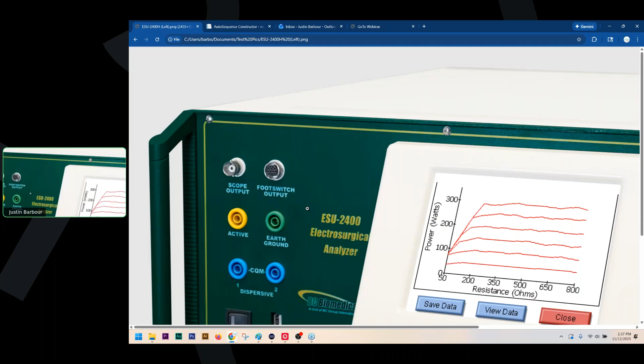And maybe from there it tells you, okay, plug it now into monopolar port 2. And it automatically will set your ohms for your load. Let's say for your REM, it will set your ohms load internally, and it will walk you through - did it alarm, did it alarm, did it alarm - and when it finally alarms, that's when it gives you a pass or fail condition. We can do it automatically.